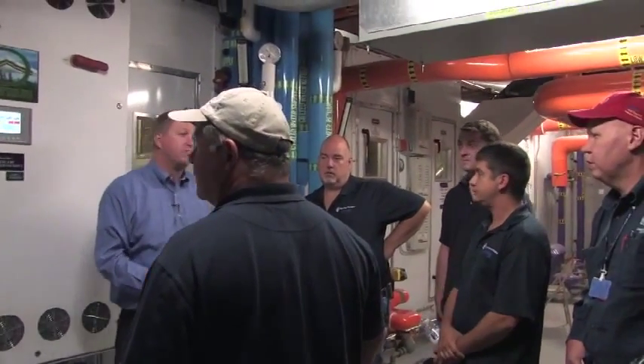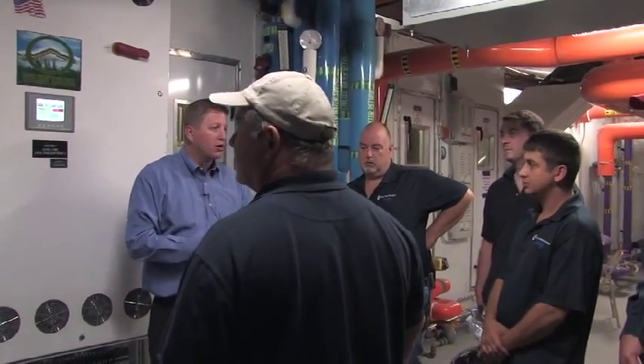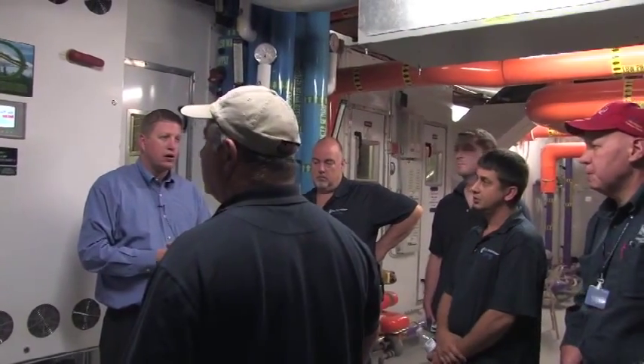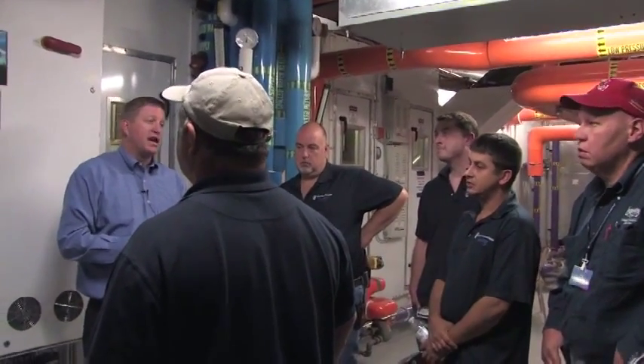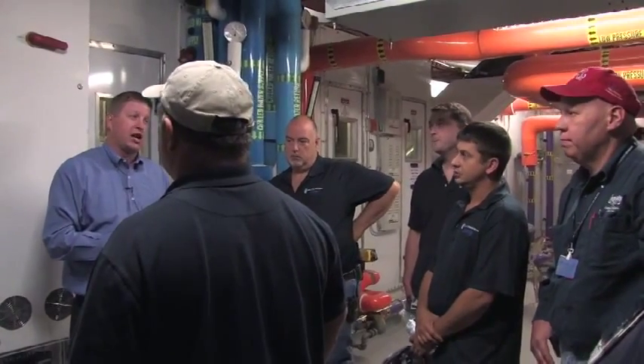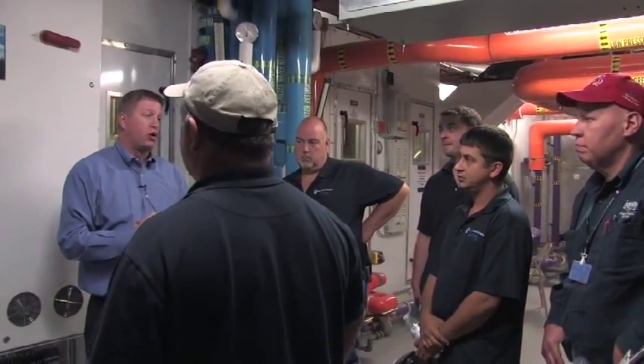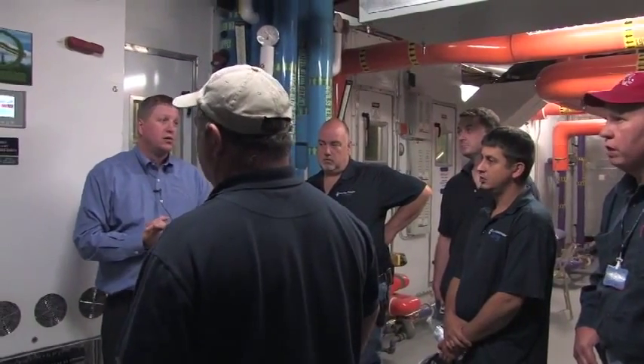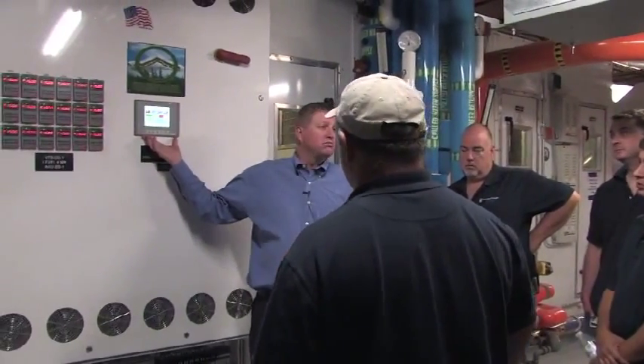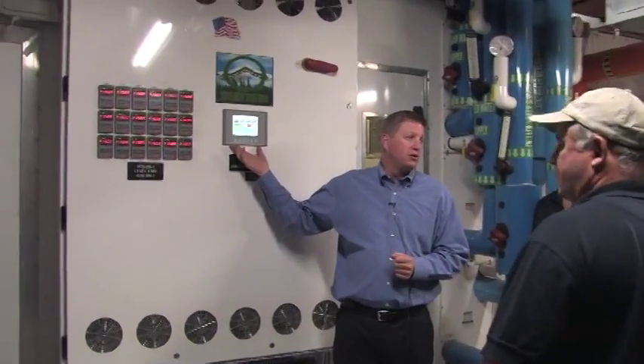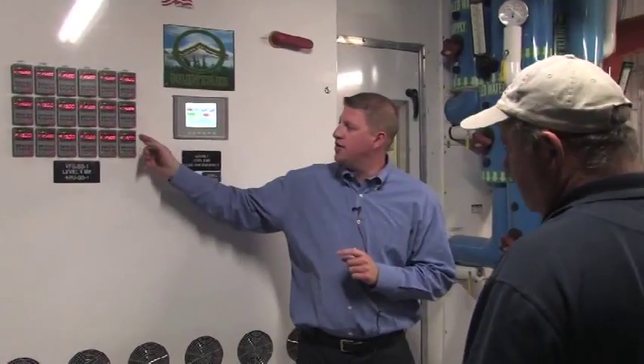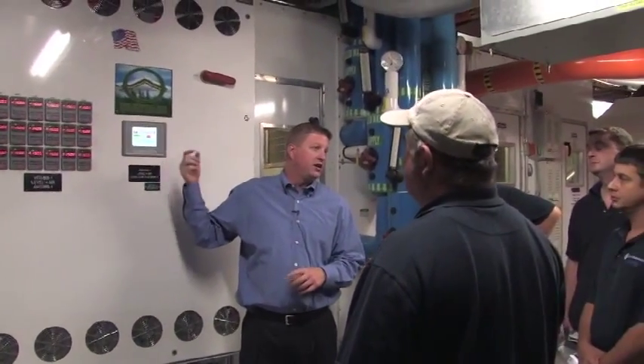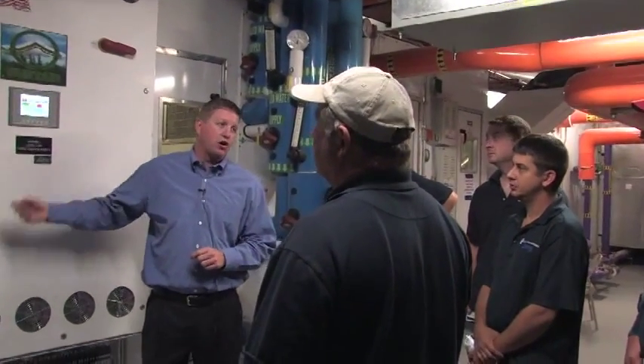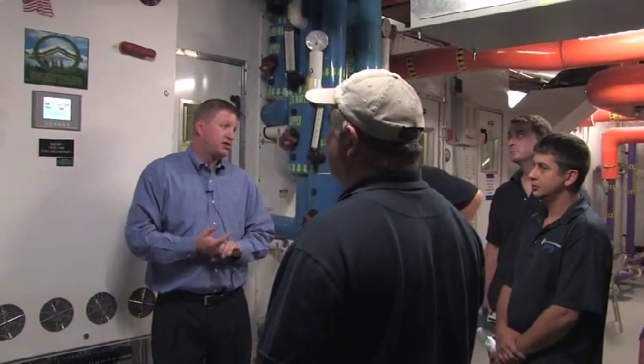If you didn't have anything, like I said, there's a way we can get it on, as long as you have power. Those don't operate together. Not at that level, no. I mean, that's your worst. That's your last. You've had a lot of things go wrong to get down to that level. To run it in hand like this, yes, which is pretty typical. If you're down to this level, you've had a failure on your BMS, you've had a failure on this touch screen, and on top of that, probably a failure with our controls logic inside it. That's deep.